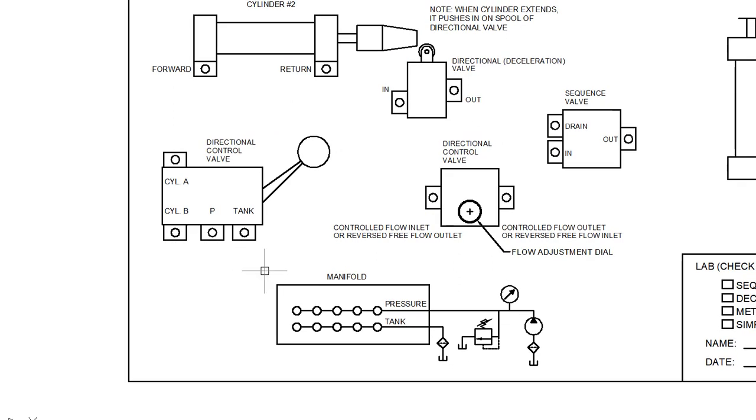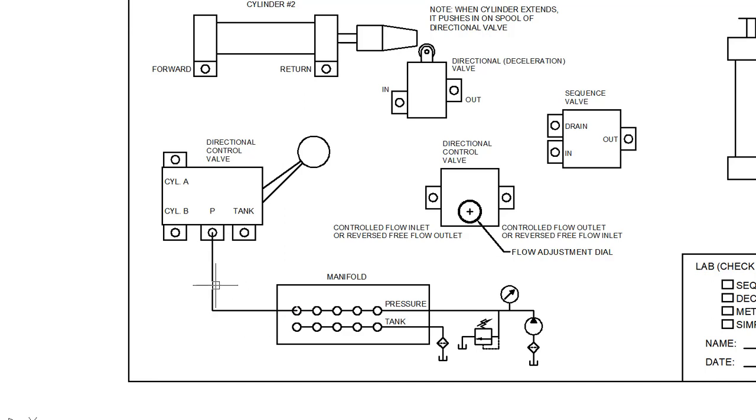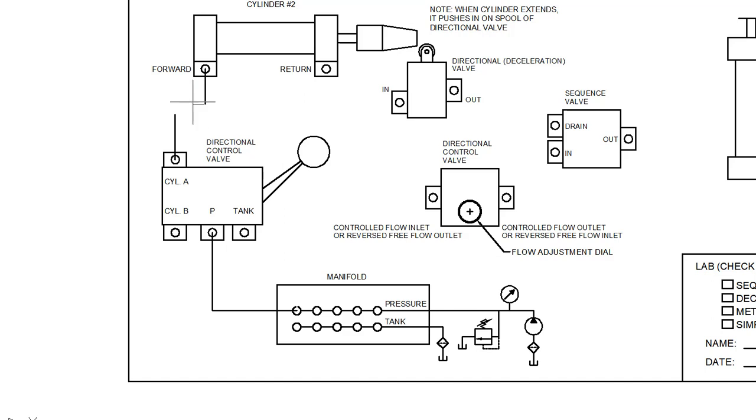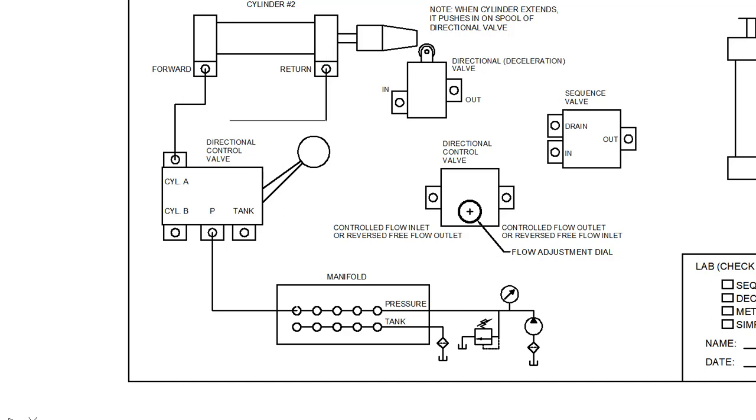If we're going to hook up that circuit, we'll hook the pressure up to the pressure ports on the manifold. Then cylinder A is going to be our forward, that's the A side there, and then the B side is the return side, so we have to get those lines to cross.